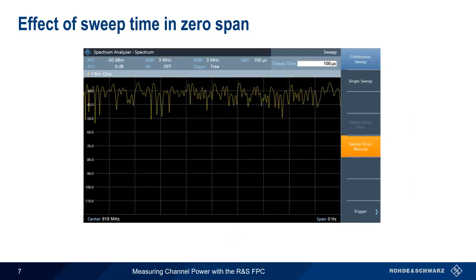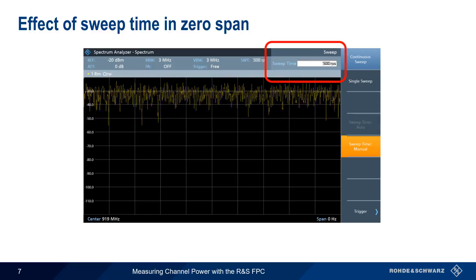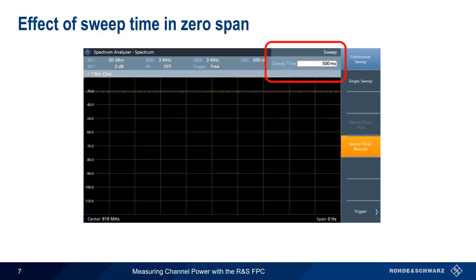One important parameter when measuring channel power using zero-span is sweep time. Generally speaking, increasing the sweep time will improve the stability and repeatability of our measurement results, although obviously this will also increase measurement time.